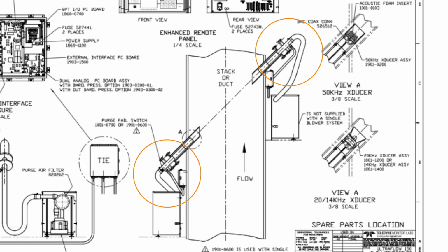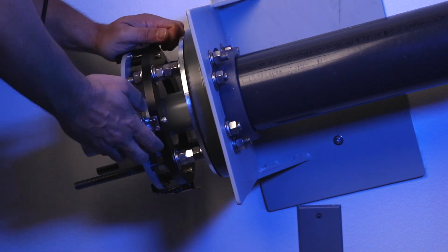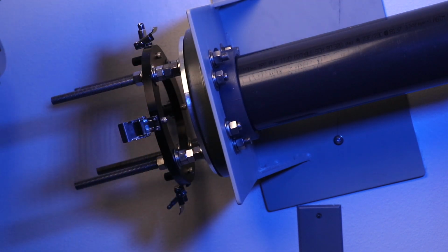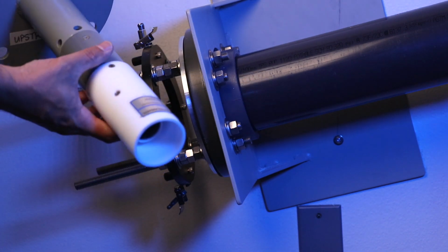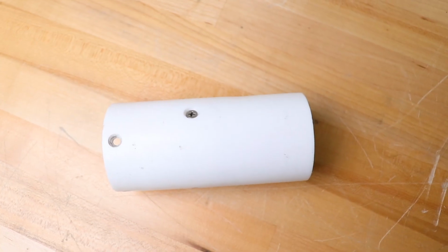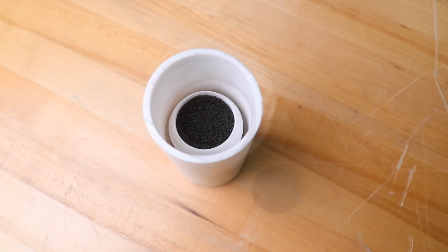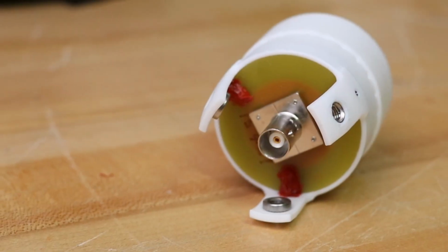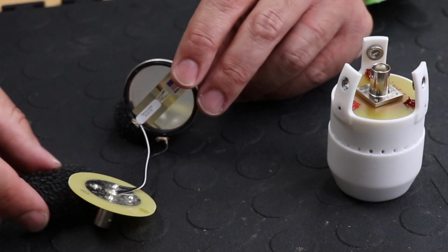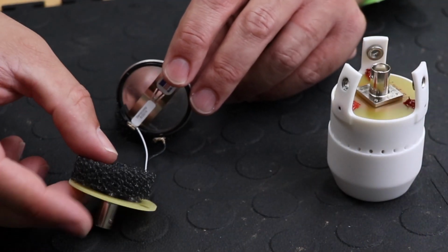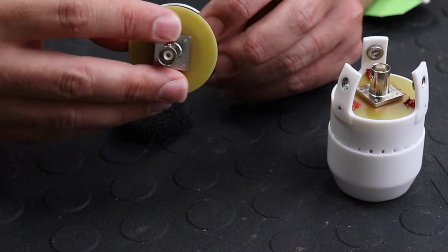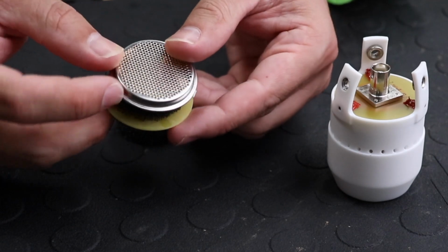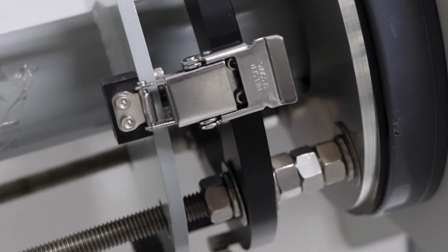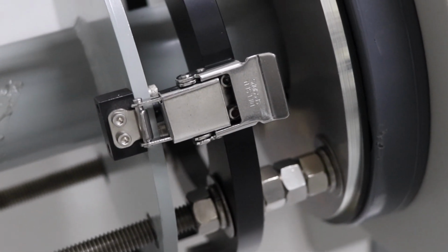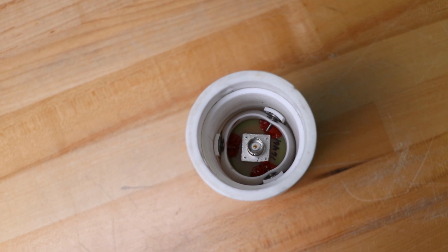Next, the purge nozzle assemblies located on opposite sides of the stack or duct. Each houses an ultrasonic transducer and is designed to provide protective purge air around the transducer to prevent contamination from the effluent gas stream. The purge nozzles are constructed using Teflon, stainless steel, and other corrosion-resistant materials to provide a long service life. The actual transducer element is housed in a transducer housing subassembly and is located near the end of the purge nozzle nosepiece. The stack geometry, wall thickness, and mounting details determine the length of the purge nozzle assemblies. A quick disconnect latching mechanism secures the assembly to the threaded rods. Connections are made by BNC connector to both transducers by coax cable.